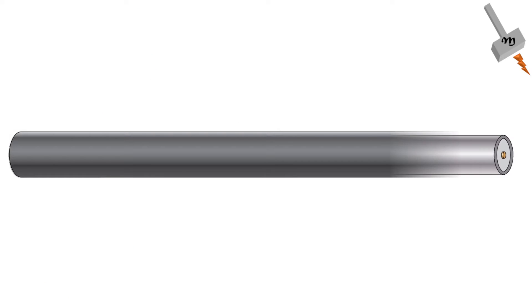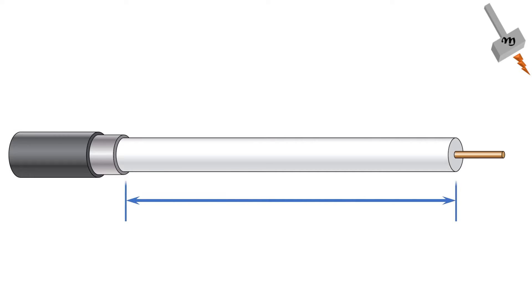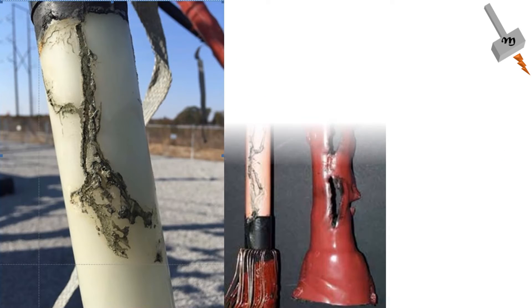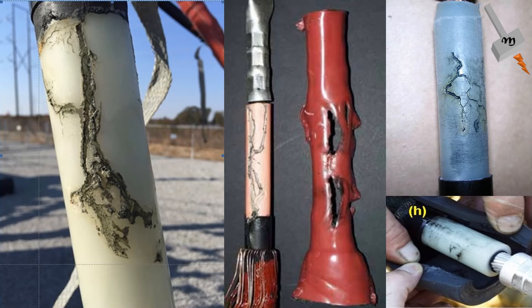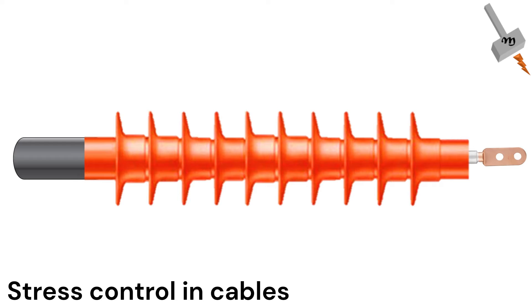When an HV or MV cable needs to be terminated, the shield needs to be removed for a distance to expose the center conductor. If the shield is not sufficiently stripped back, the small distance between conductor and shield is not sufficient to prevent flashover or surface tracking. While this elevates flashover concerns, the electric field distribution around the conductor axis is distorted — the field is no longer symmetrical and now congregates around the edge of the grounded shield. The high electric field stress near the cable shield discontinuity will eventually cause localized insulation overstress that can lead to cable damage. Steps need to be taken to control the electric field when terminating MV and HV cables — this is known as electric stress control.